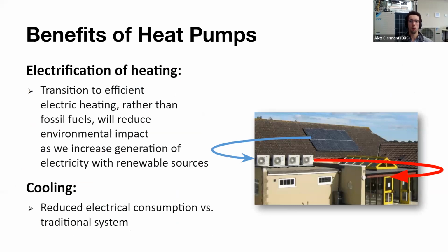Now, why use heat pumps? What's the benefit? So heat pumps are actually used in cooling everywhere. We'll talk about efficiencies of the different types of heat pumps for cooling, but electrifying heating is really where heat pumps come into play. With electric heat, 1 kilowatt of heat from the grid gets you 1 kilowatt of heat. With heat pumps, you can move about 2 to 5 from the grid. So you actually get more heat from the heat pumps than you're drawing from the grid. And if you're using electricity, you can use clean electricity, whether that's from the grid or from on-site generation.